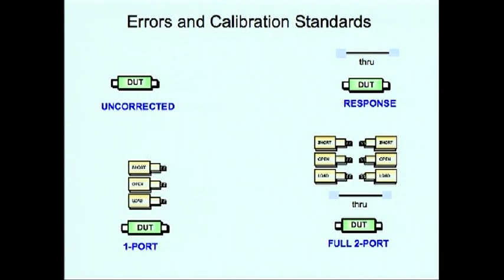When the highest accuracy is needed, a full two-port calibration is done. The full two-port calibration removes errors like directivity, source and load match, reflection tracking, transmission tracking and cross-talk. We will now do a full two-port calibration.